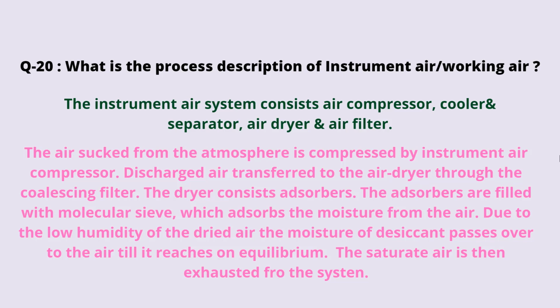What is the process description of instrument air or working air? The instrument air system consists of an air compressor, cooler and separator, air dryer and air filter. The air sucked from the atmosphere is compressed by the instrument air compressor. Discharged air is transferred to the air dryer through the coalescing filter. The dryer consists of adsorbers. The adsorbers are filled with molecular sieves which adsorb the moisture from the air. Due to the low humidity of the dried air, the moisture of the desiccant passes over the air till it reaches equilibrium. The saturated air is then exhausted from the system.